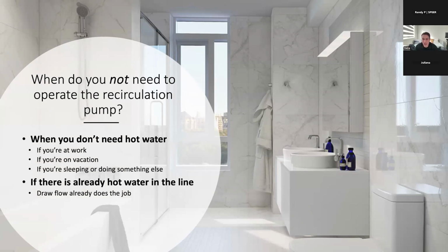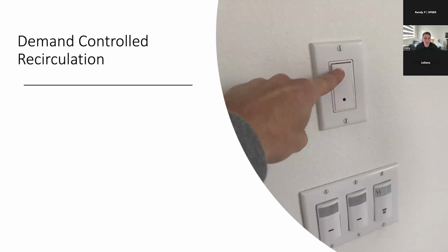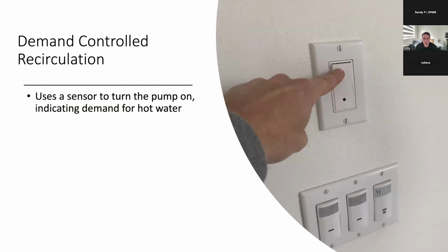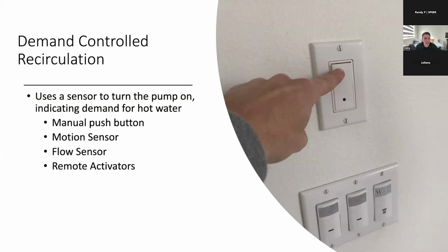And once draw flow is moving the hot water through your pipes and it reaches the end, the pump does not need to be running. So you only need to turn on the pump just before you need it. And that's what demand recirculation controls do. It uses a sensor or a switch that indicates the demand for hot water to turn the pump on. And this can come in different forms. It could be a manual push button. It can be a motion sensor.